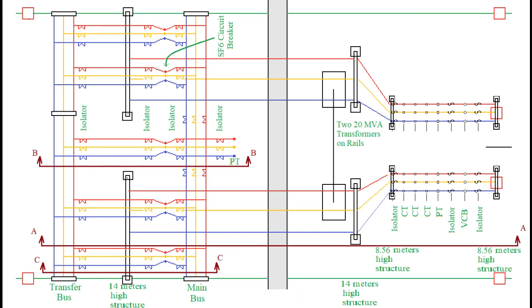The next component of the substation to be considered is the potential transformer. These transformers are one group of 3 for measurement purpose and another group of 3 for protection purpose. In this way, a total of 6 potential transformers are required and could be seen above line BB. These PTs are generally 132 kV by 110 volts. We will number them as EHT PT1 to EHT PT6.